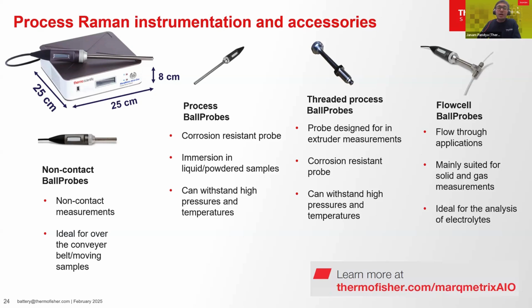The process ball probe is a contact probe manufactured using Hastelloy material, which can withstand corrosive and oxidative chemicals in the environment. It can be utilized to measure slurries, liquids, and powder samples, and can withstand high temperatures and pressures. The threaded process probe is specifically designed to fit in the extruder, either on the die end or mid-barrel. It can also withstand high temperatures and pressure, and is commonly utilized to monitor extrudate uniformity or to monitor reactive extrusion.